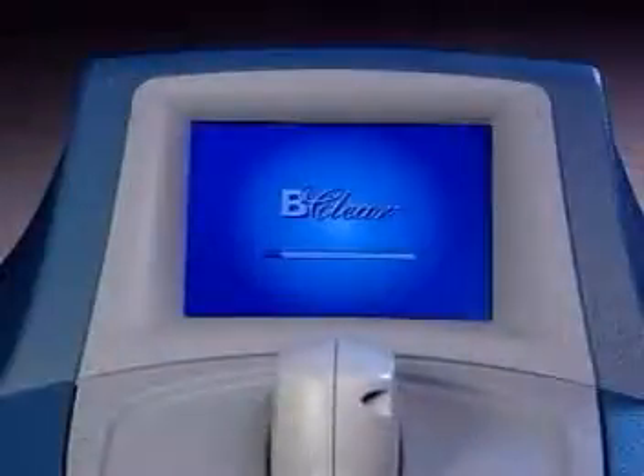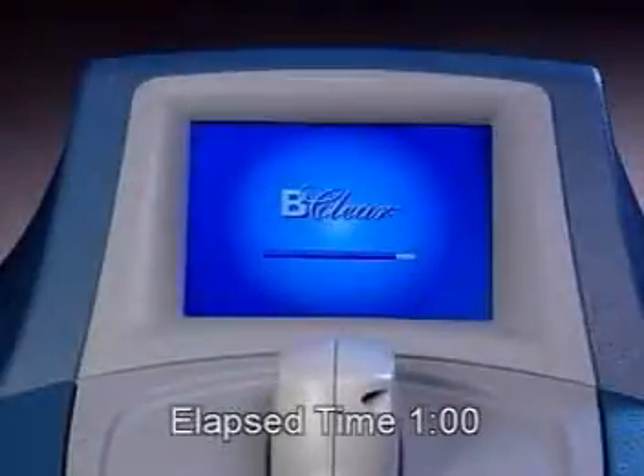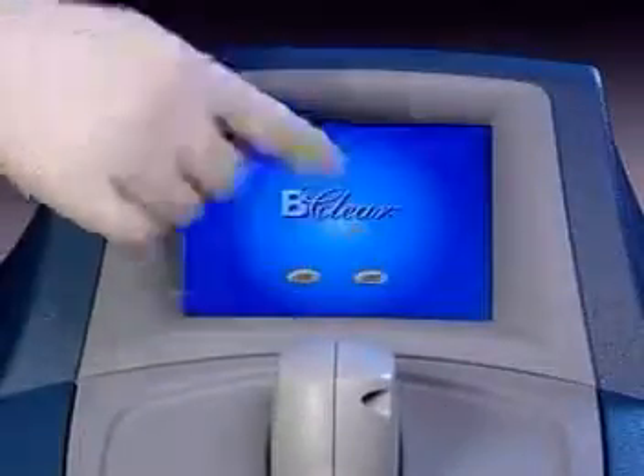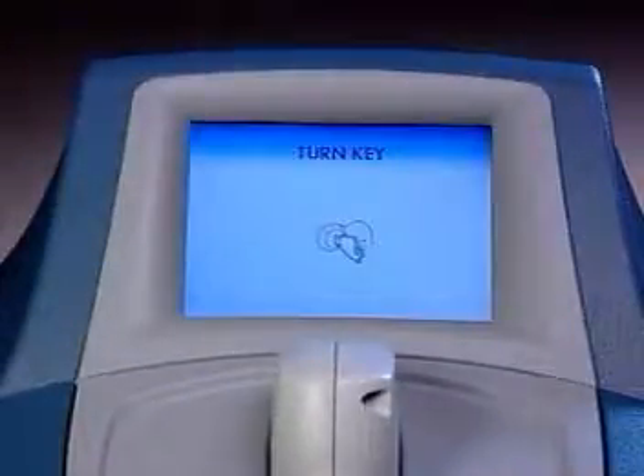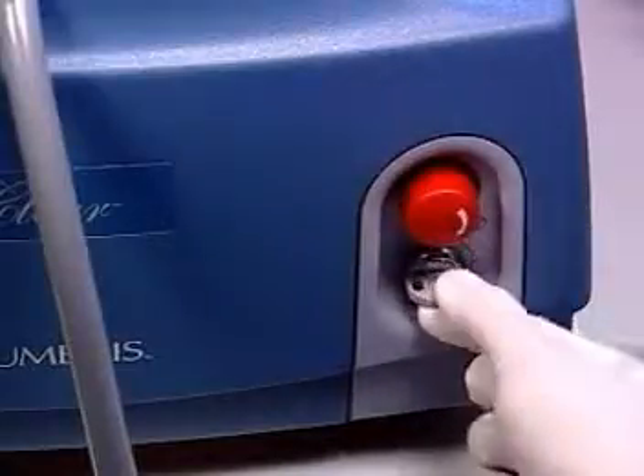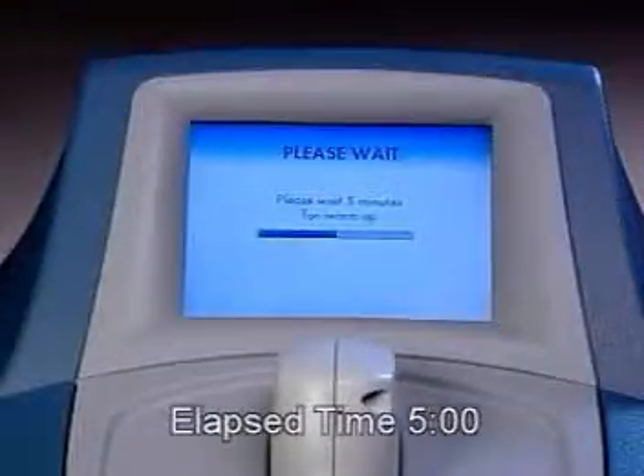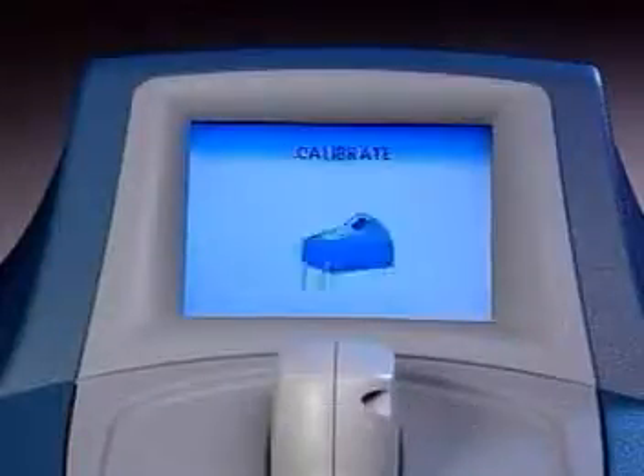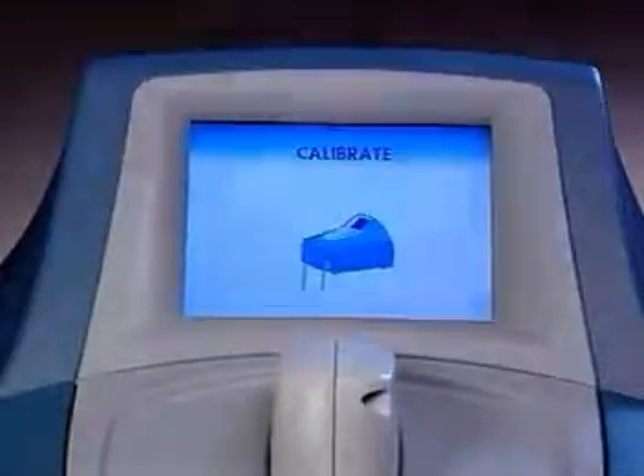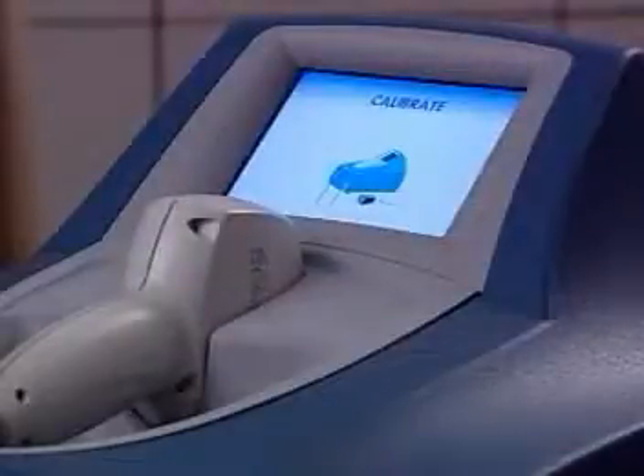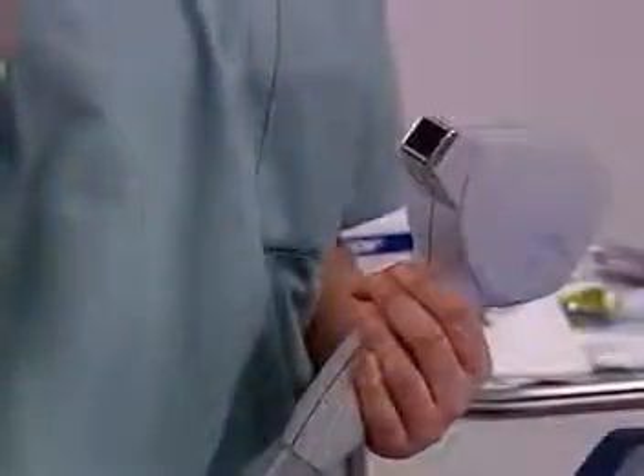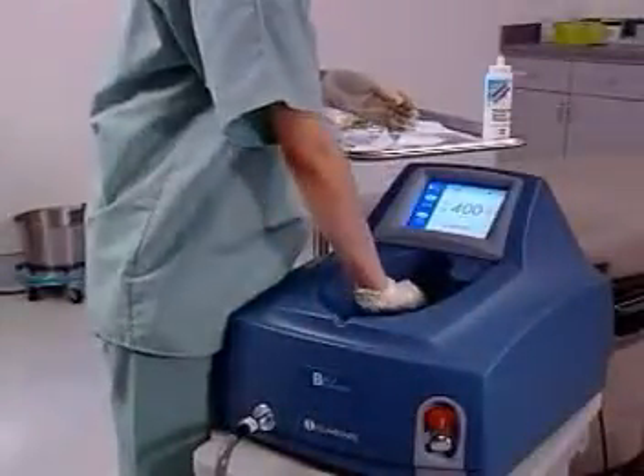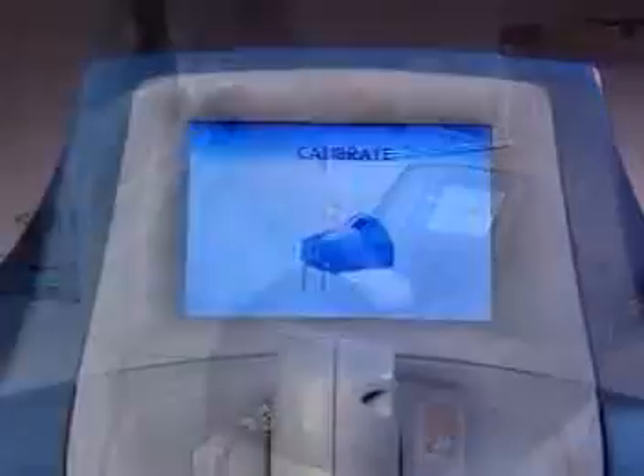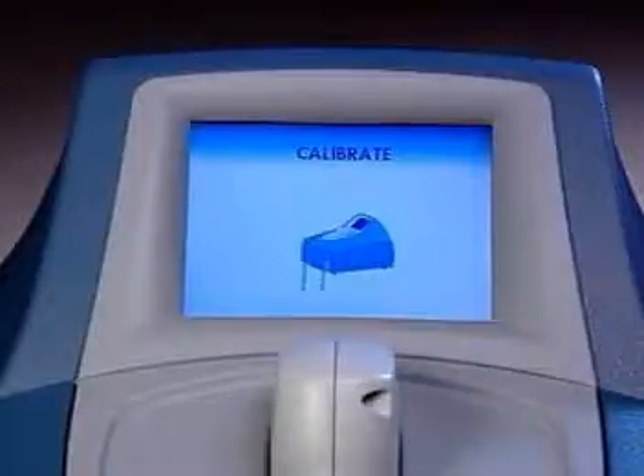The microprocessor performs a self-test that takes about a minute. Press Start on the startup screen. When prompted, rotate the key switch to the on position. The system takes about 5 minutes to warm up. The calibration screen will appear. A calibration check is required each time the power is switched on and should also be performed prior to each new patient. For accurate calibration, the handpiece tip and energy meter window must be clean and free of moisture and debris. The calibration screen will guide you through calibration.